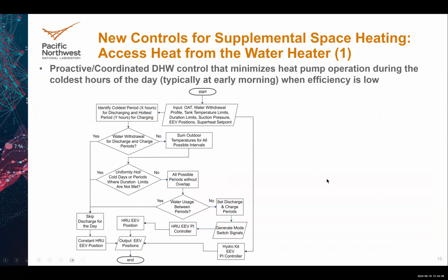So I have the last part of my presentation about the controls. We have the model ready, we have a calibrated model, right? How can we control the system to achieve the objective like I mentioned? How can we still maintain our space air temperature during very cold weather conditions? So basically, we are trying to coordinate the domestic hot water control to minimize heat pump operation during the coldest hour of the day. Typically, in the early morning, like maybe 5 or 6 a.m., when efficiency is lower.